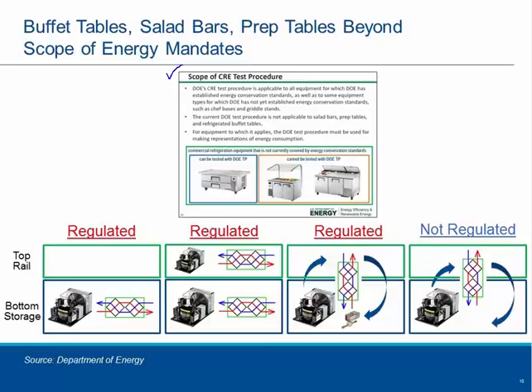We dug in a little more to really understand what that architecture is about. In some of this equipment that many of you are familiar with, there is a top rail, similar to what you see in a salad bar and a buffet table, where it's kind of open. Then you have a bottom storage area where a condensing unit is providing cooling capacity for some more storage. If you have a system where the top rail is not sharing or having its own condensing unit, but the bottom storage is, this would almost be classified as an undercounter, and there is, in fact, a test procedure for it.